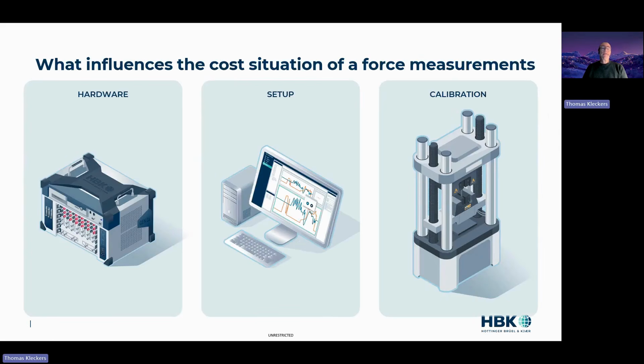So, if you talk about the costs of a force measurement chain, you have to keep an eye on 3 points. First of all, you have to invest into hardware. You need to buy a sensor, a signal conditioner, cable, or whatever. Second thing, and very often forgotten, is that you have a certain setup process. So you need to mount the sensor into your assembly line, into your production line, into your test rig, wherever it ends. And finally, it is really recommended to have a calibration from time to time. All of these factors are costs. And now let's have a look at the difference between the old world and the new world.